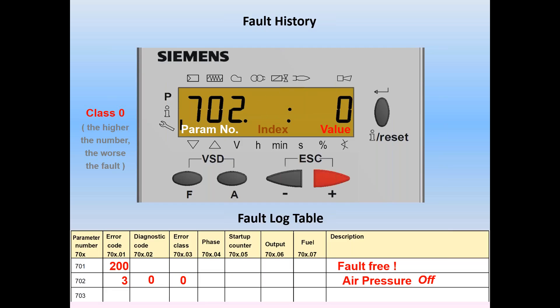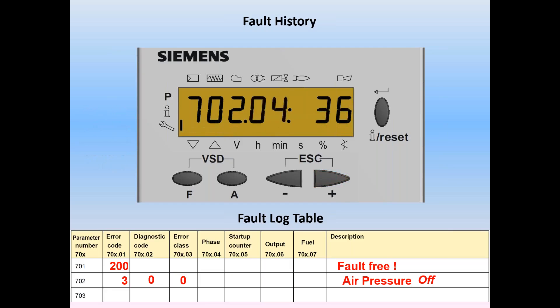Do a plus and we move to the next index, 04, which gives us a value of 36. This is the phase in which the problem occurred. Phase 36 is 'drive to the ignition position' — that's when the error occurred, when we drove the air damper down to low fire for ignition. We enter value 36 into the chart at column 04.